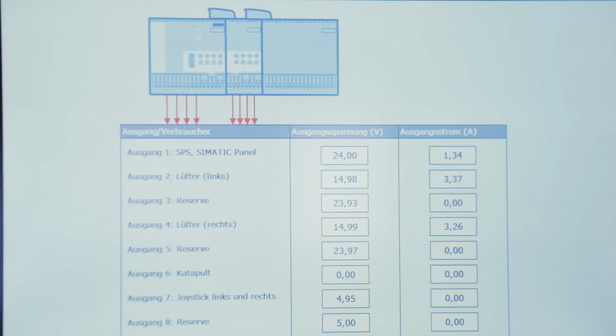The adjustable output voltage can be used to not only supply 24 volts to consumers. With this model, for instance, we supply the manual controls with 5 volt and the solenoid with 8 volt DC voltage. You don't need any additional power supplies. In industrial applications, the dynamic voltage supply isn't only used for ventilators, but also for DC motors at small conveyors.